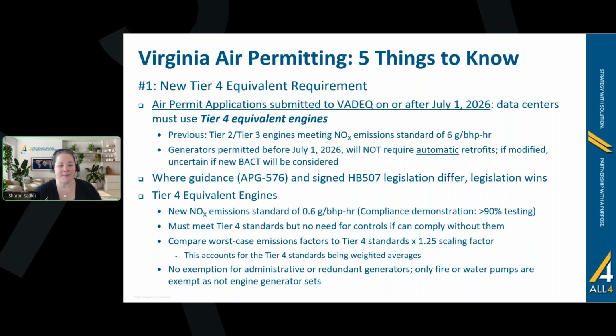Another thing where the legislation is less flexible than the guidance might have been is with administrative or house generators, those redundant generators. In the guidance document from DEQ, it talked about how maybe those don't need to be Tier 4 equivalent, maybe there can be some flexibility there. But the legislation doesn't provide that. It just says engine generator sets need to be Tier 4 equivalent. So even if that's a 500 kW house gen or something, it will need to meet the Tier 4 equivalent standards starting July 1st and forward.